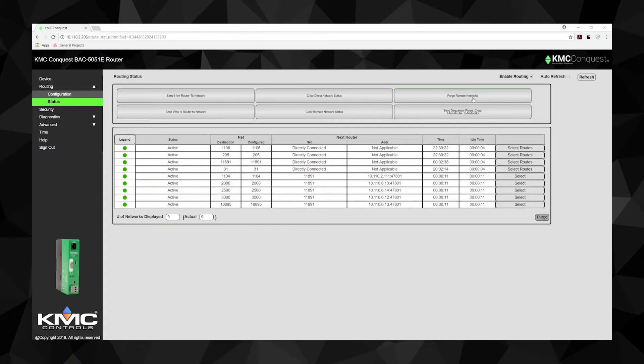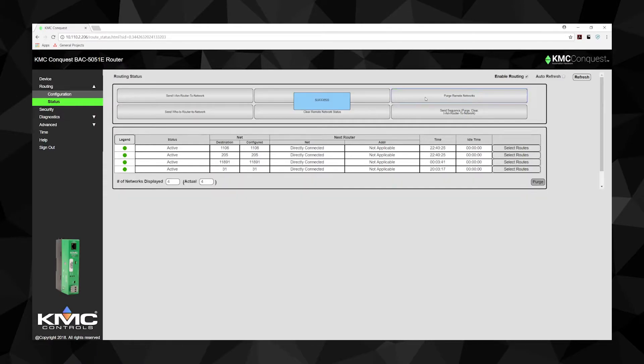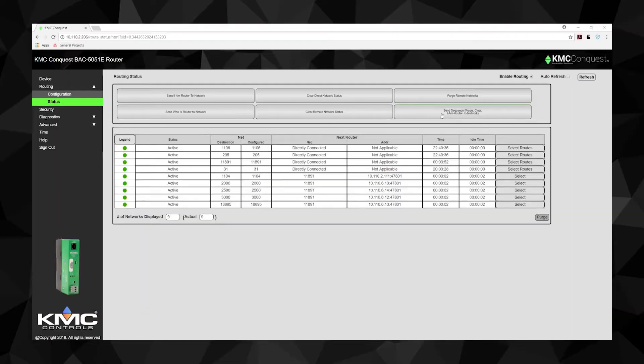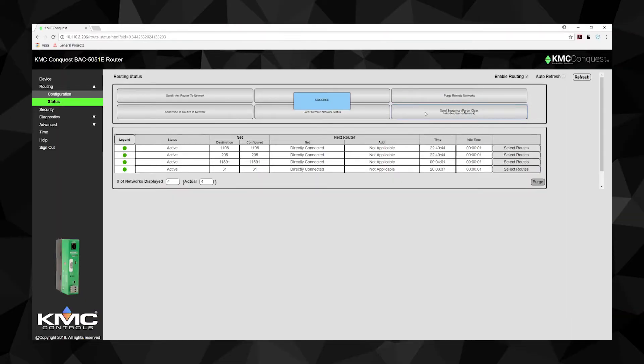Purge Remote Networks removes all of the remote routers from the network table. Send Sequence broadcasts three commands in order — Purge, Clear, and I Am Router to Network — in order to trigger a table update.